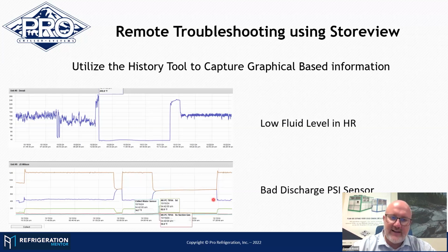And we're looking at things and we're like, we're operating and then we trip. I can't see off to the side, but I think we were at like 1300 psi. We're well away from 1600. And so the condition was present. It was reset manually on site. We operate, everything is looking perfectly normal. And then all of a sudden, boom, we trip. Now we're off, things have equalized. The guy goes out and resets it again. Everything's running normal. Boom, it trips again for no particular reason.